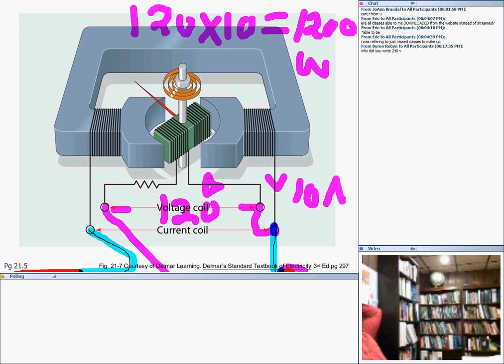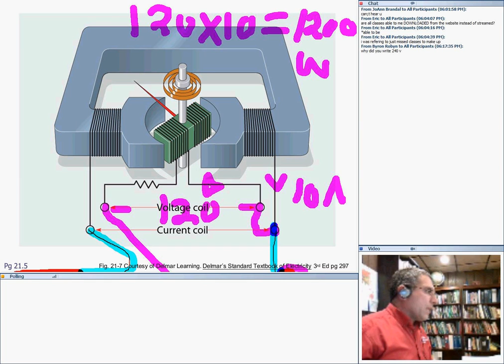One coil for voltage and one for the current, and then you capture a movement based on both the voltage and the current, and calibrate this movement. Remember, this movement is based on two coils: one is the current, the other is the voltage, and the two coils will diverge to move the indicator appropriately to indicate the amount of power. So in a case like this, this will be calibrated as 1200 watts. The scale is calibrated, but the movement this time is based on two coils.